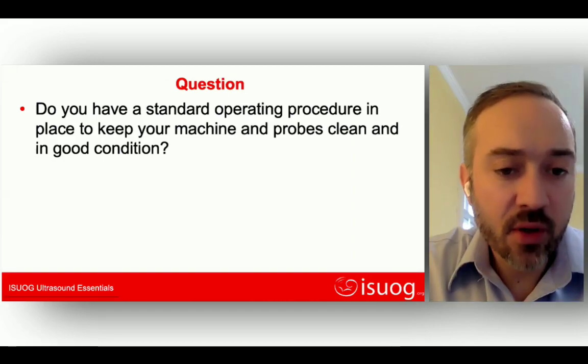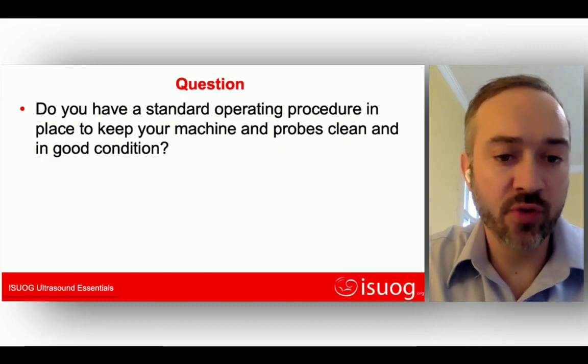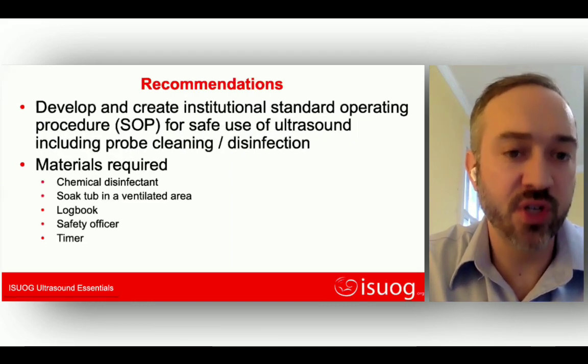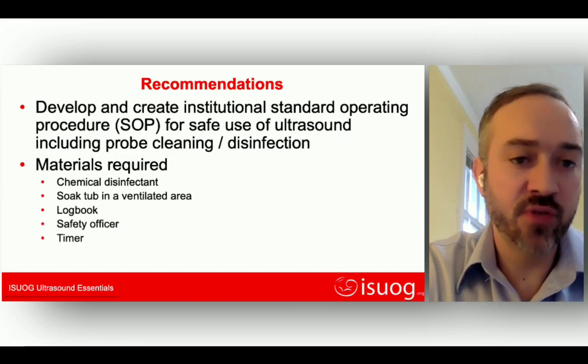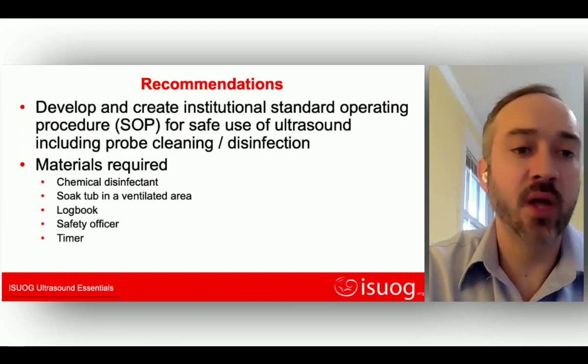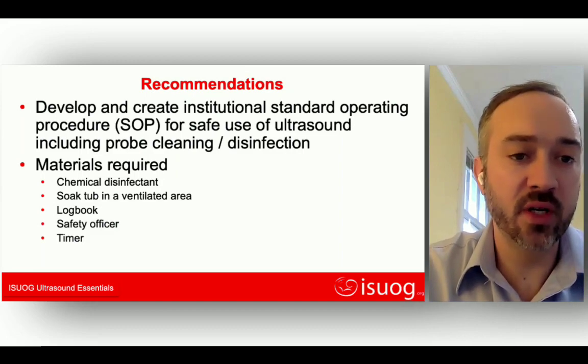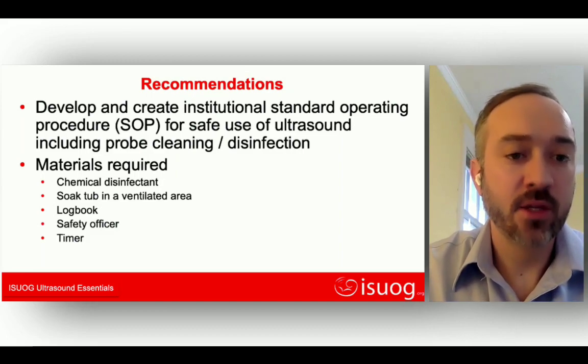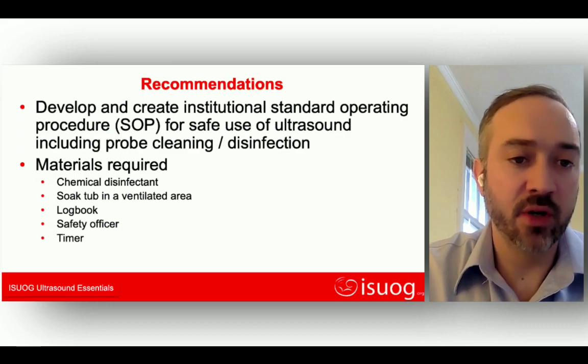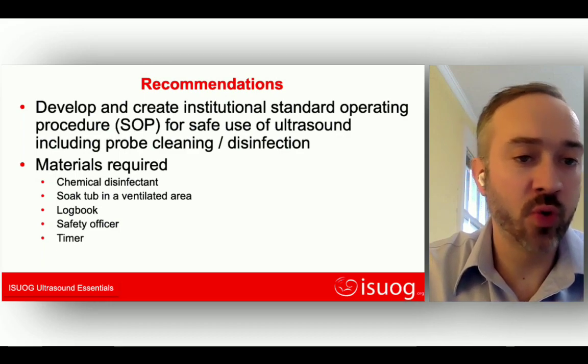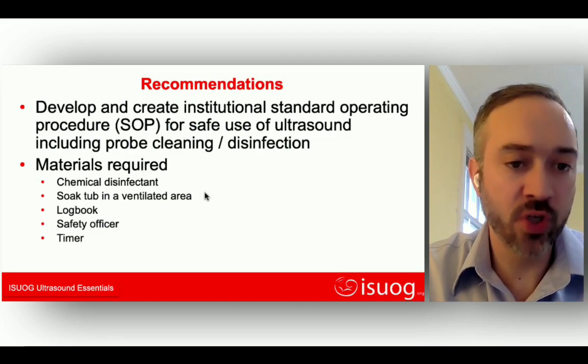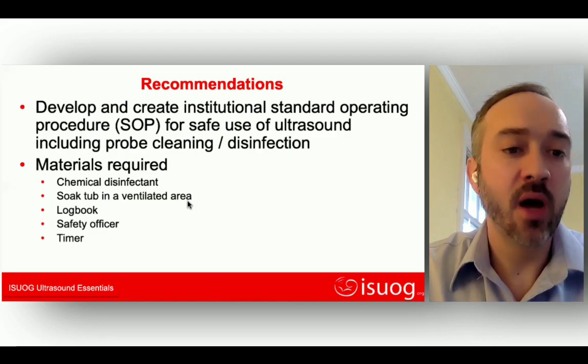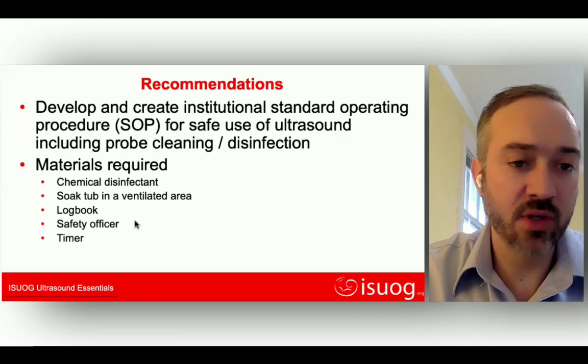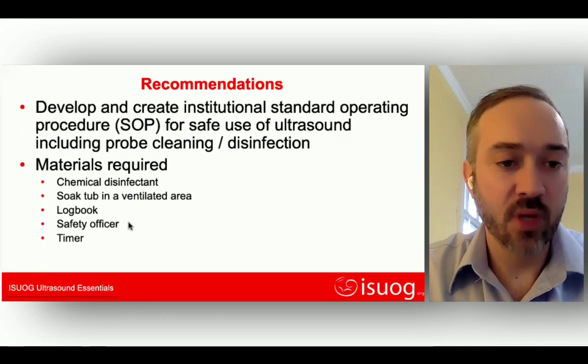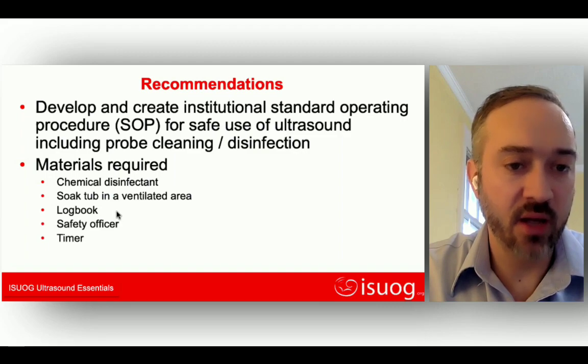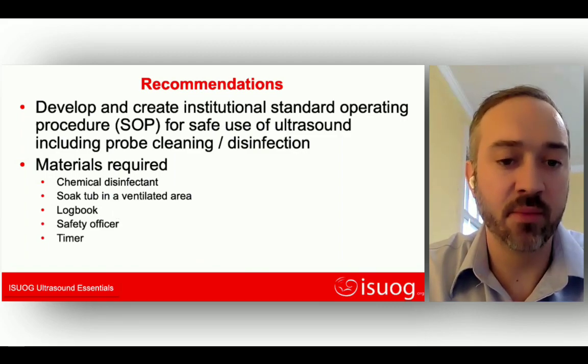So we would recommend that you develop a standard operating procedure for the safe use of your ultrasound probe, and include how you clean it and how you disinfect it. This will vary depending on your setting, but basically the materials required will be your disinfectant, a soak tub if you're using a chemical soak, a logbook to keep track of it, somebody who monitors this logbook, and a timer if you're using the soak time method.